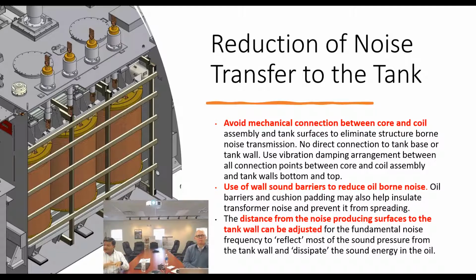So if there is any vibration coming from the core and coil assembly, now there is a damper which will absorb the vibration, and then a reduced amount of vibration is passed to the tank wall. And that's how the direct or structure borne transmission of the vibration to the tank wall has been reduced. Now we do the same thing at the bottom of the transformer, because the transformer core and coil is sitting in the tank bottom, so we can damp the connection point over there. We can damp the connection point on the top, and that makes the total core and coil assembly, or vibrating element, damped for the transformer tank arrangement.